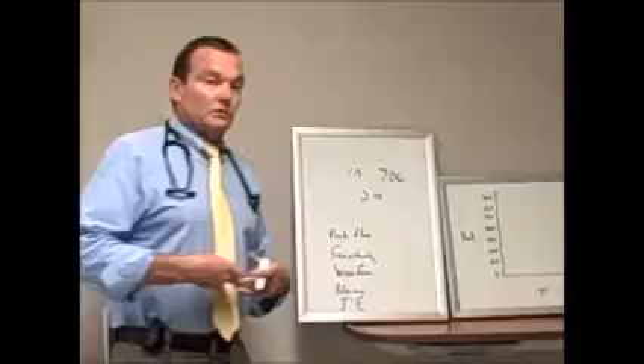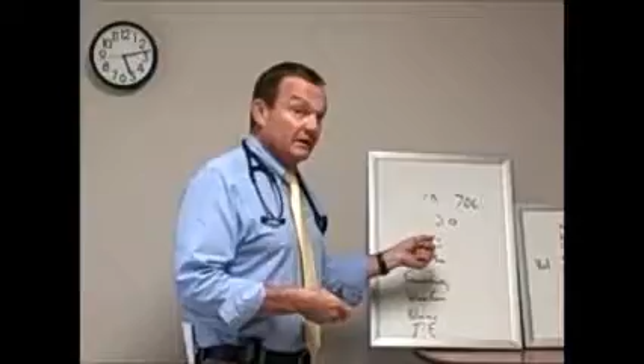Okay. So if you have it on a sensitivity of 2.0, when he starts to inspire and generates a negative pressure of 2 at the ventilator circuit, then the demand valve opens and the ventilator takes over the work of breathing. So if it's 1.0 or 1.2, that's not much work of breathing. I've seen them. You walk in, sometimes the patient's going, and the machine's not triggering. I've seen them on 10 and 20.